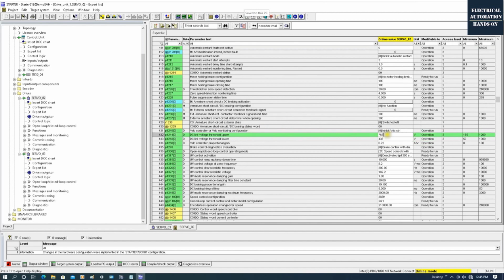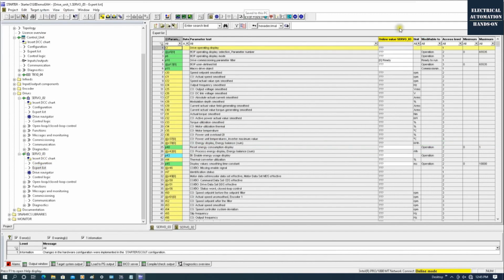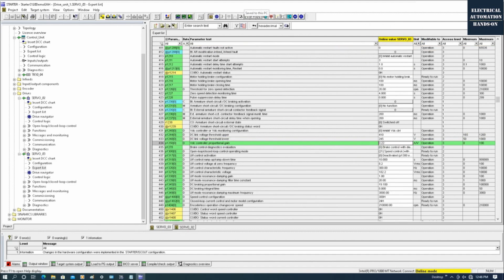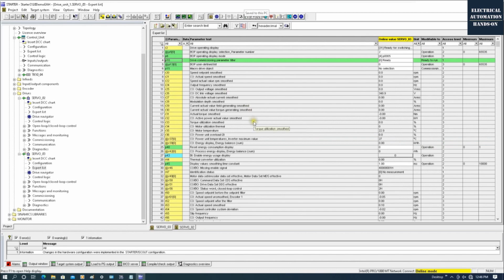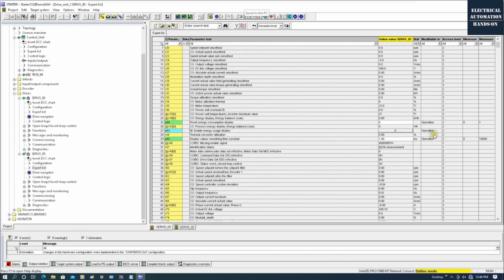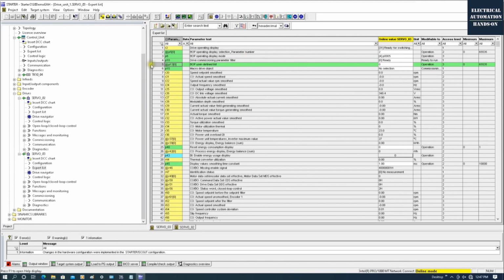And then let's go to P1244. You can type in 1244. And from here, we can set the DC bus voltage, the upper and the lower threshold, because our input voltage is lower than the regular voltage, that's 600. So we need to also adjust this DC bus, DC link voltage. And then let's go to the P10. This is a drive commissioning parameter filter. Let's double check if that's set 0.